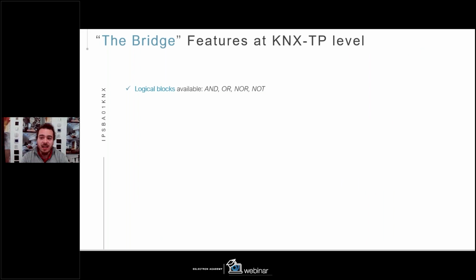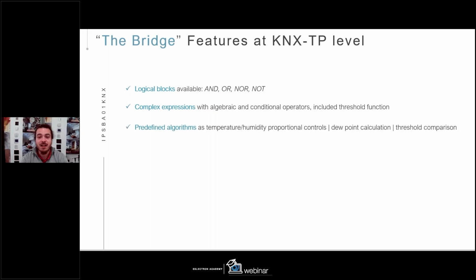So, as said at the beginning, inside the bridge we will also find some logic, starting from common logic like AND, OR, NOR, NOT logic gates. But we will also have complex logic expressions with the math operations we can perform, conditional operators, thresholds, and so on. And also the scenario conditional that we saw in the previous webinar, like the if then else: if this happens, do that, otherwise send this other value on the output. We will have some predefined algorithms like the dew point calculation or the conversion between a proportional fan coil and an on/off fan coil or vice versa.